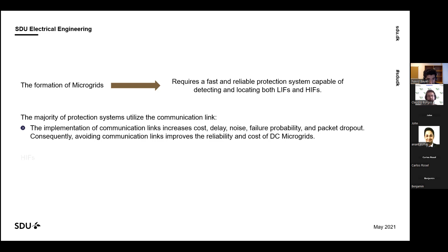So normally, in DC microgrids, we can make our own protection system, and the protection systems are different. They can work locally, or they can work through a communication link. If we are talking about working with a communication link, the communication link can increase costs, delays, noise, failures, and packet dropout. So normally it's better to work on protection systems that avoid the communication link and are local.